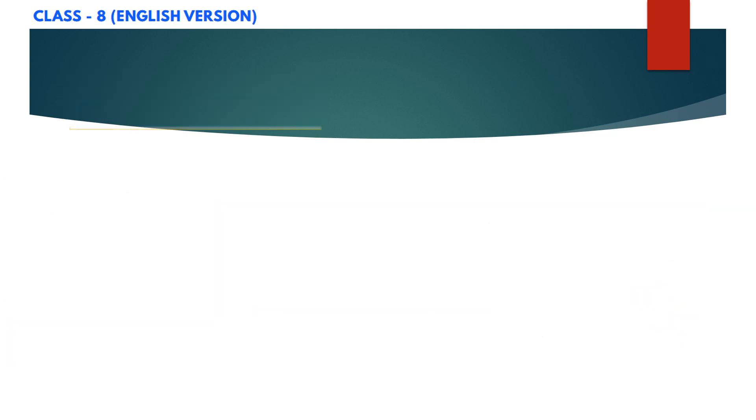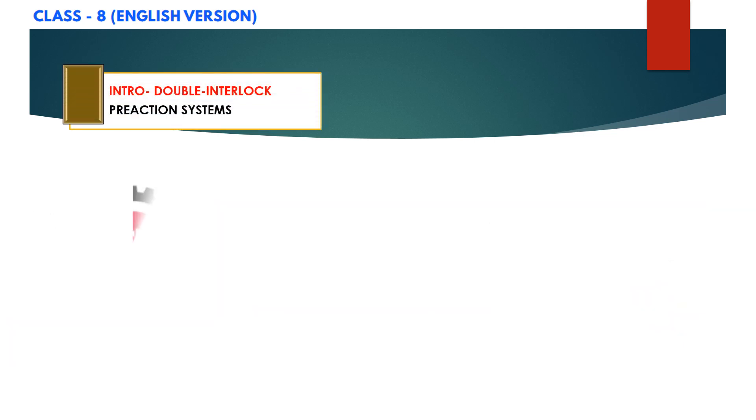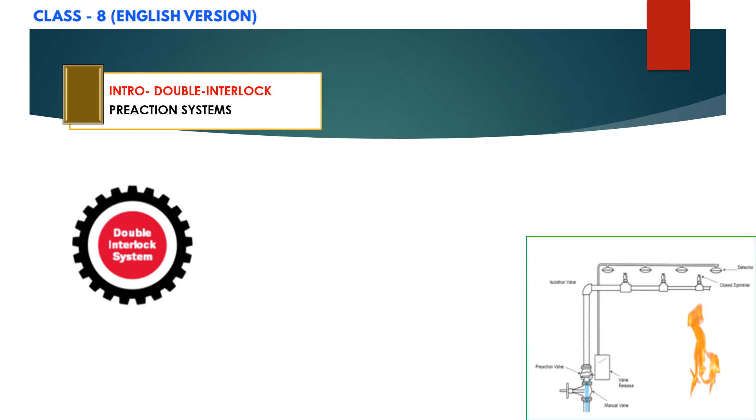Now let us go through double interlock preaction systems. In double interlock preaction systems, as you can see on your screen, preaction valve will only activate upon operation of both the detection devices and these closed sprinklers.